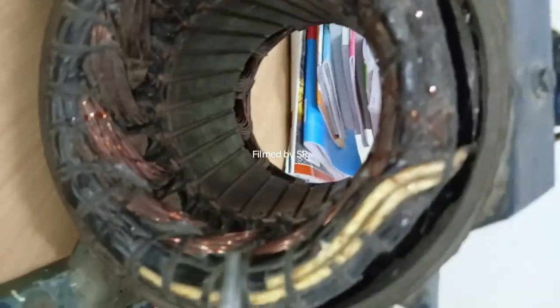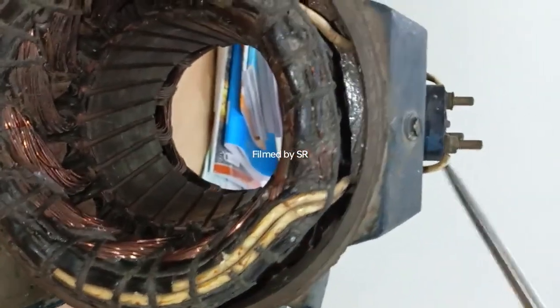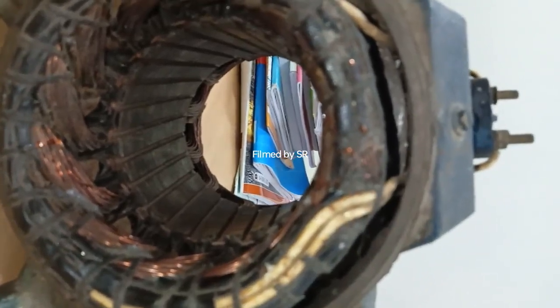These solid, heavy wires are actually the terminal wires that are connected to this top part. Actually this is a delta connected machine, so we are having 3 terminals getting out of our machine. Had it been a star connected machine, we would have 4 terminals for our stator available here.